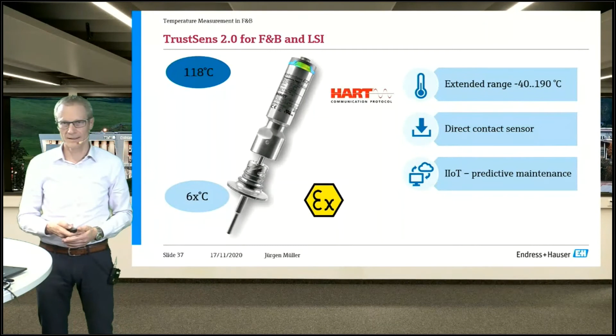So in fact, I would like to come to a conclusion and to mention the most important takeaways for you that I talked about in my presentation. You see, I show you here 4 pictures. So the first one is the well-known QuickSens, and keep in mind this is the sensor with the shortest response time on the market, so that you can always keep the process safety at a very high level because you can detect temperature changes within very short time. The T and elbow pieces with a special design, no dead legs, no welding, they just help to keep product and process safety at a high level so that you don't need to worry about cleaning and having problems with contaminations and stuff like that.